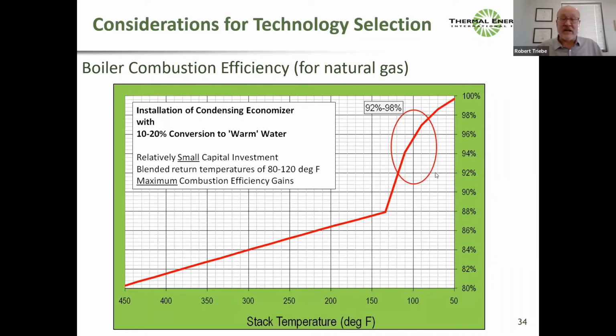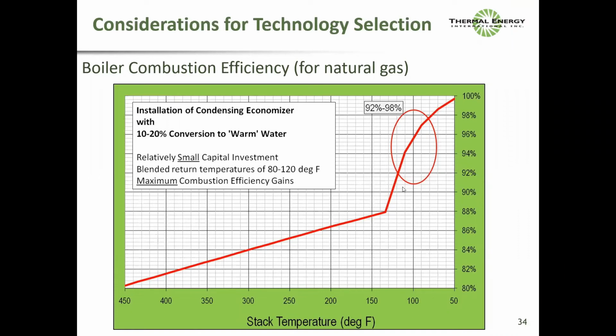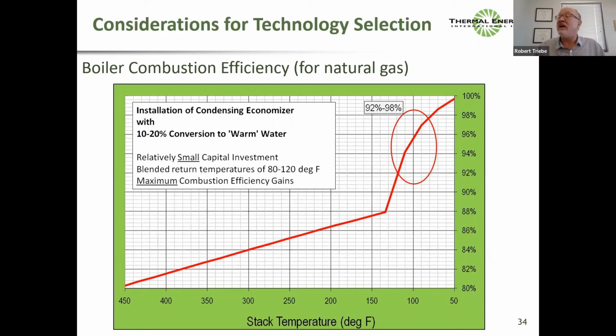Yeah, now you're getting into modeling, and we'd have to look at how things are balancing out. But the bottom line is, if you have water users down at 120 or 110, then yeah, having a condensing stage is going to dramatically increase your efficiency. And that can be done either, again, in an indirect or a direct fashion. But that's a controls question, where we would run that water. But yeah, you wouldn't want to run the 120 through the traditional hydronic, because then you'd be condensing in a traditional hydronic boiler. That would be bad news.